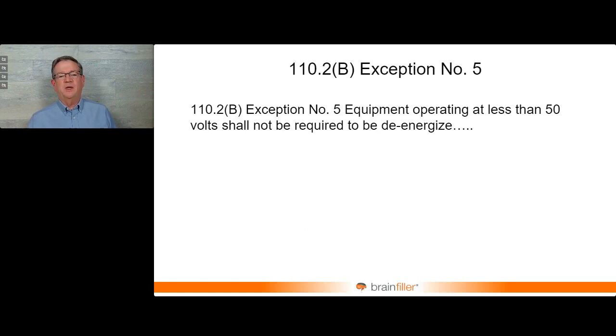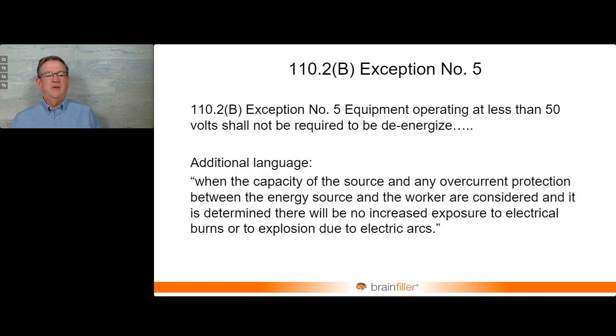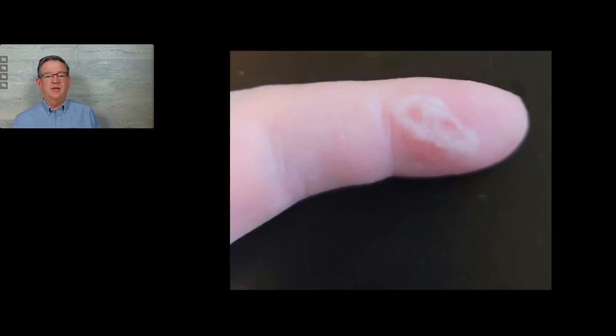Equipment operating at less than 50 volts. There was additional language added here, and this was about you have to determine that there's no increase in the exposure to electrical burns or explosions. Less than 50 volts, can there be an explosion? Never say never. I've never seen it happen. Can there be a burn? Oh yeah, you get sparks and things like that at less than 50 volts. Absolutely, there could be a minor burn injury. And so that's what this is about. Just make sure that you don't have something like this that results.